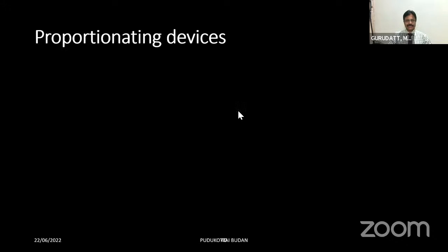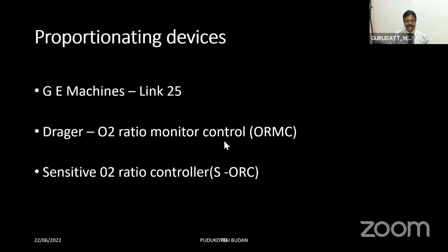These flow proportionating devices depend on the workstation you have, whether a GE workstation or a Draeger workstation. In GE machines, the proportionating device is the Link 25. In the Draeger machine, the older name was oxygen ratio monitor control, and now it is called the sensitive oxygen ratio controller. The Link 25 is almost 95% mechanical and just about 5% pneumatic, whereas the oxygen ratio monitor control or sensitive oxygen ratio control is purely pneumatic. With these proportionating devices, the minimum flow of oxygen will always be more than 25% of the total flows. You cannot give less than 25% oxygen compared to the total flows. These are also called hypoxic guards. Many times the hypoxic guards have been asked as short notes.